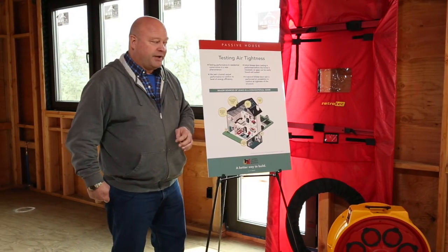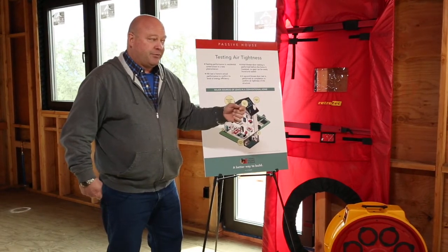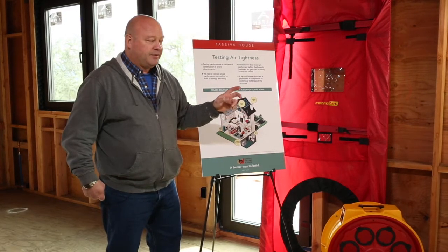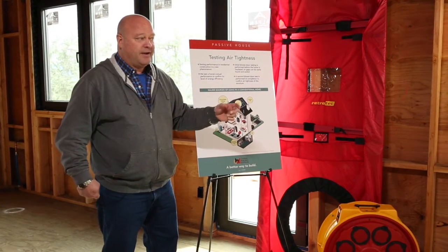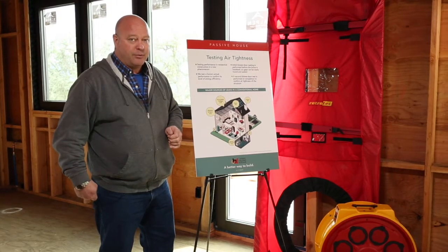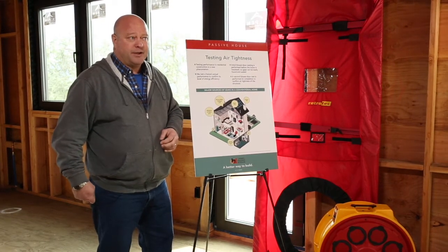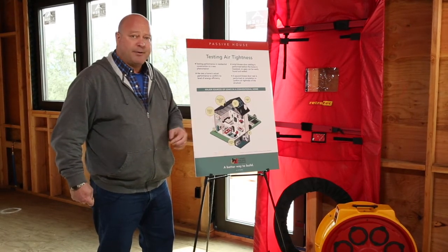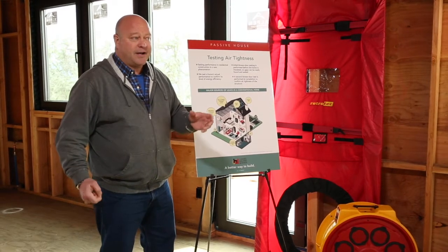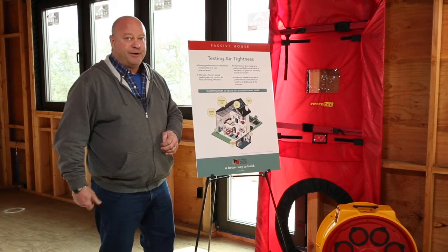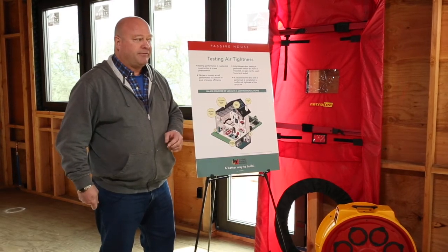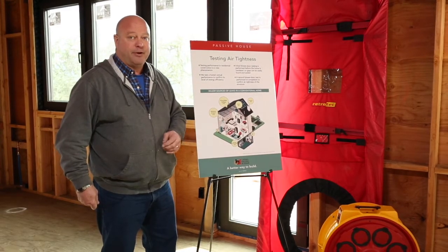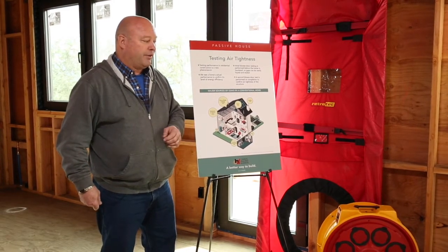Another important thing to mention here is that if air is migrating through, let's say, the walls, all air has some moisture in it, and as that air is working its way in, it might be leaving some of that moisture inside the wall. If you ever walk into a house and you immediately notice a musty or moldy smell, that's probably what's happening, and that is not good for the occupants, and it's certainly not good for the building, because that introduction of moisture oftentimes is going to lead to wood rot, which is what actually kills off a lot of buildings or gets them to the point where they're no longer usable.